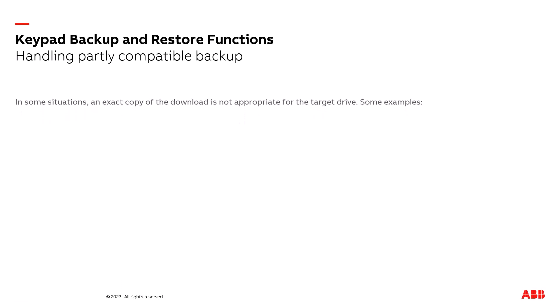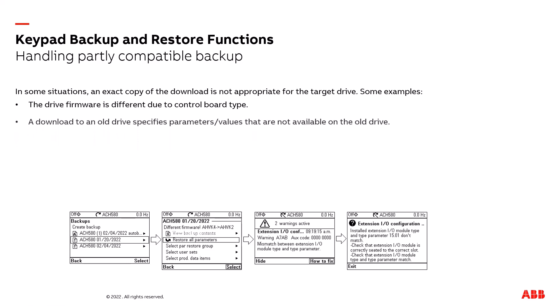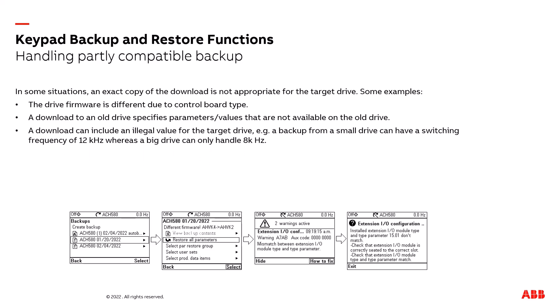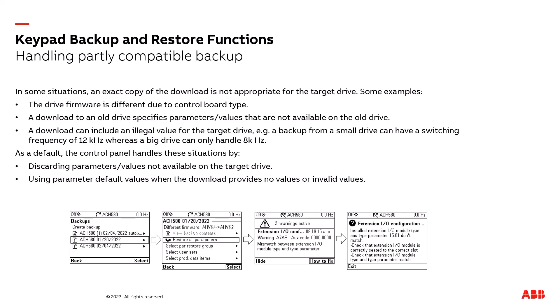Handling partially compatible backups: in some situations, an exact copy of the download is not appropriate for the target drive. Some examples are the drive firmware is different due to the control board types, or a download to an old drive where specified parameters are not available. A download can include illegal values for a target drive — for example, a backup from a small drive that can have a switching frequency of 12 kilohertz, whereas a bigger drive can only handle 8 kilohertz. As default, the control panel handles these situations by discarding parameters not available on the target drive, using parameter default values when the download provides no value or invalid values, and providing warnings on how to fix the information.